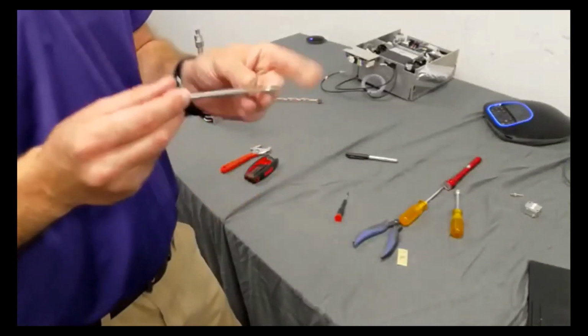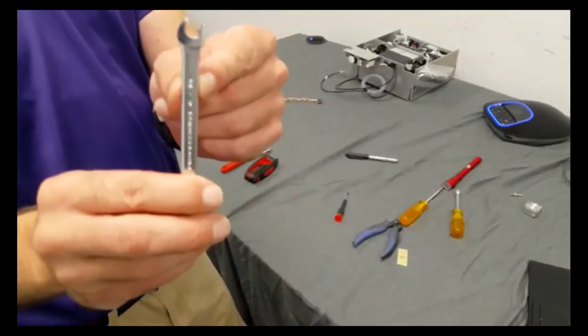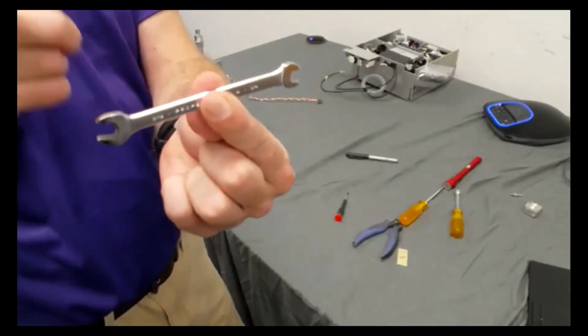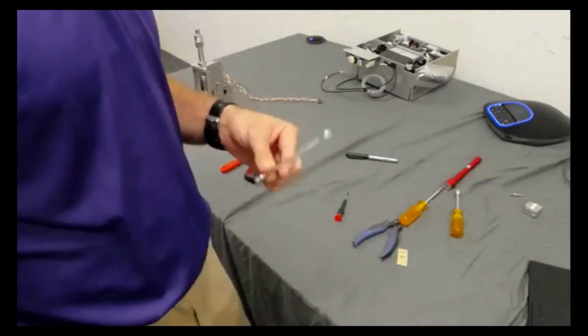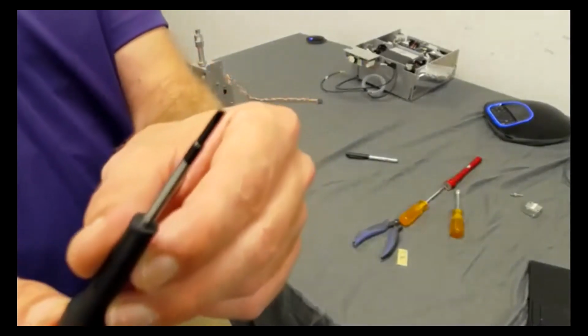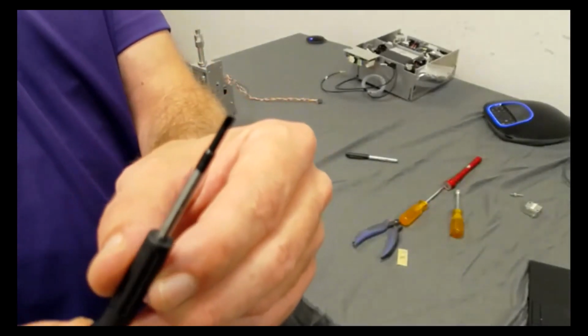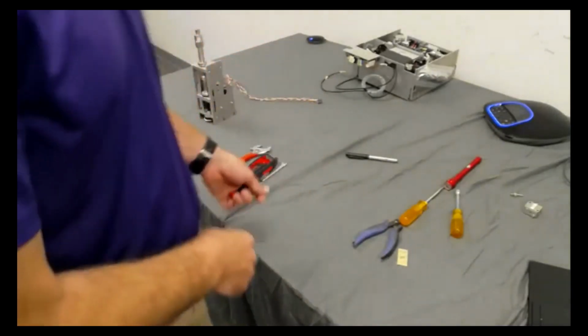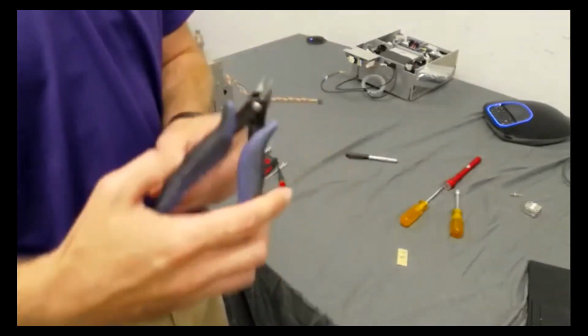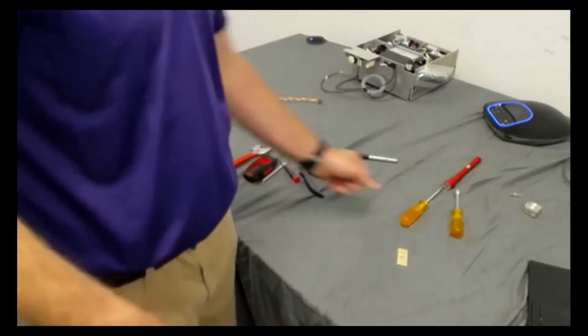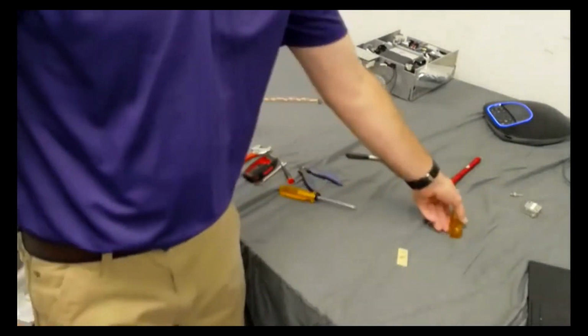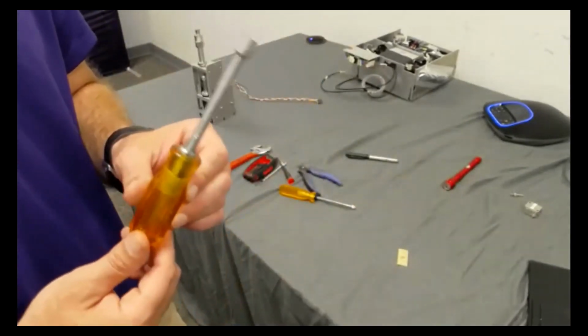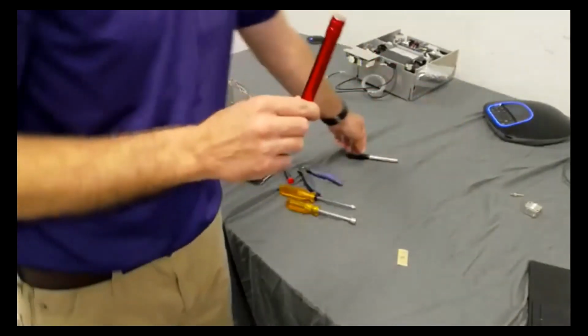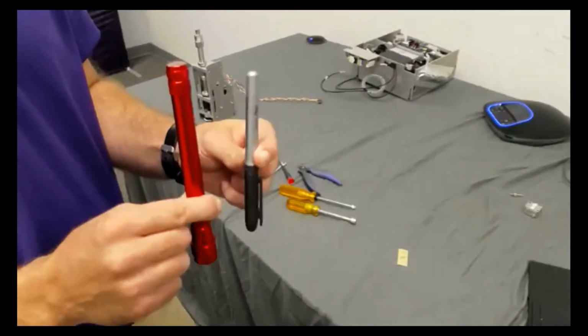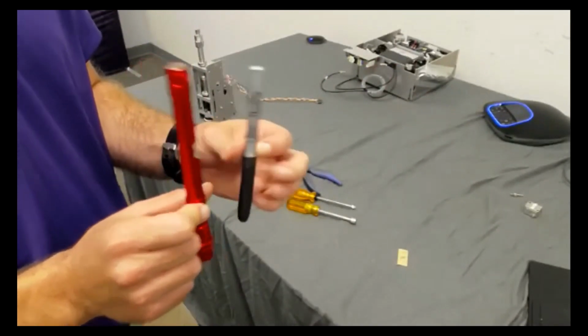You want a 5/16 wrench, and you want a 1/4 inch wrench. All right, so this one has both. I have a 5/16 and a 1/4. So basically, you're starting to see that we run off a lot of standard measurements for our nuts and bolts. You want a small flathead screwdriver, and you'll see why when I get to the pump seals, but I use this on the seals. This is a valuable tool for the seals. Side cutters, because there will be zip ties from time to time. So you want to have them. Phillips head screwdriver. 5/16 or 8mm nut driver. I like to have a flashlight and a marker. Now these aren't necessarily 100% needed, but they come in handy, okay? So I would suggest having them.